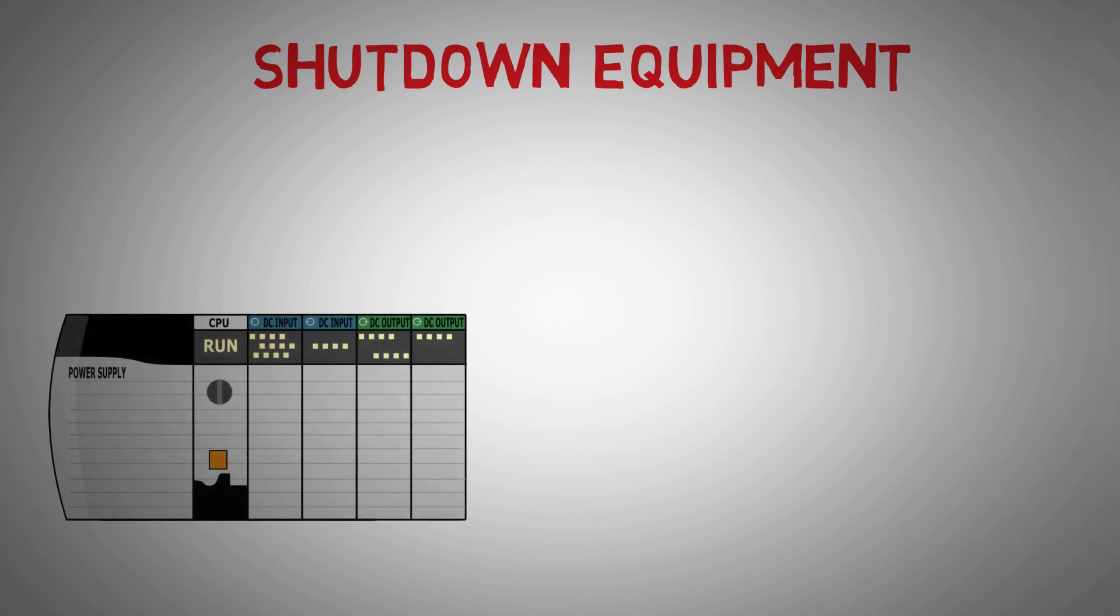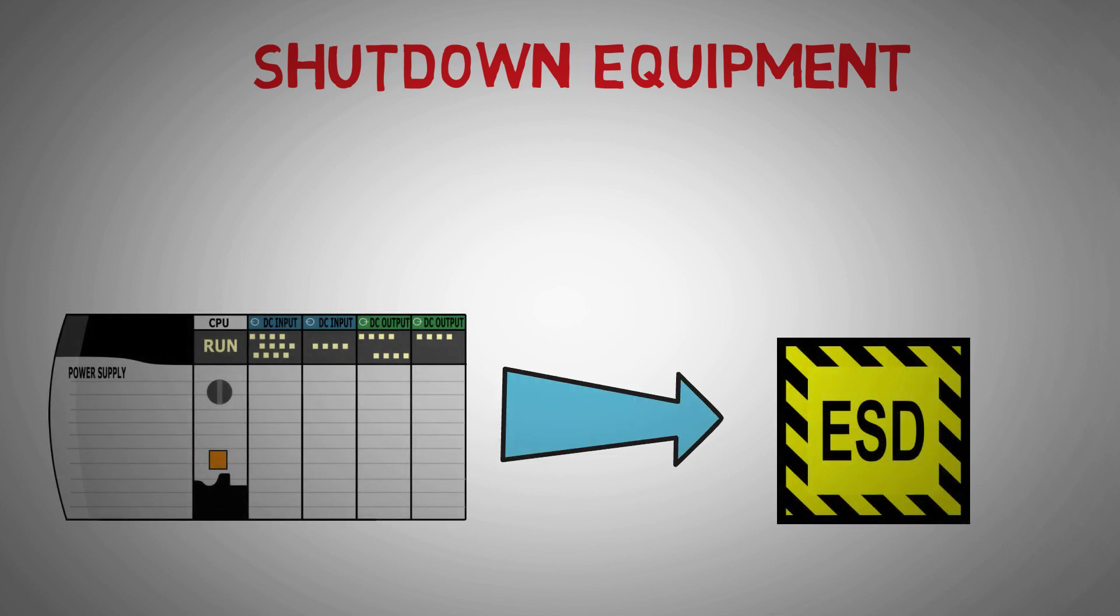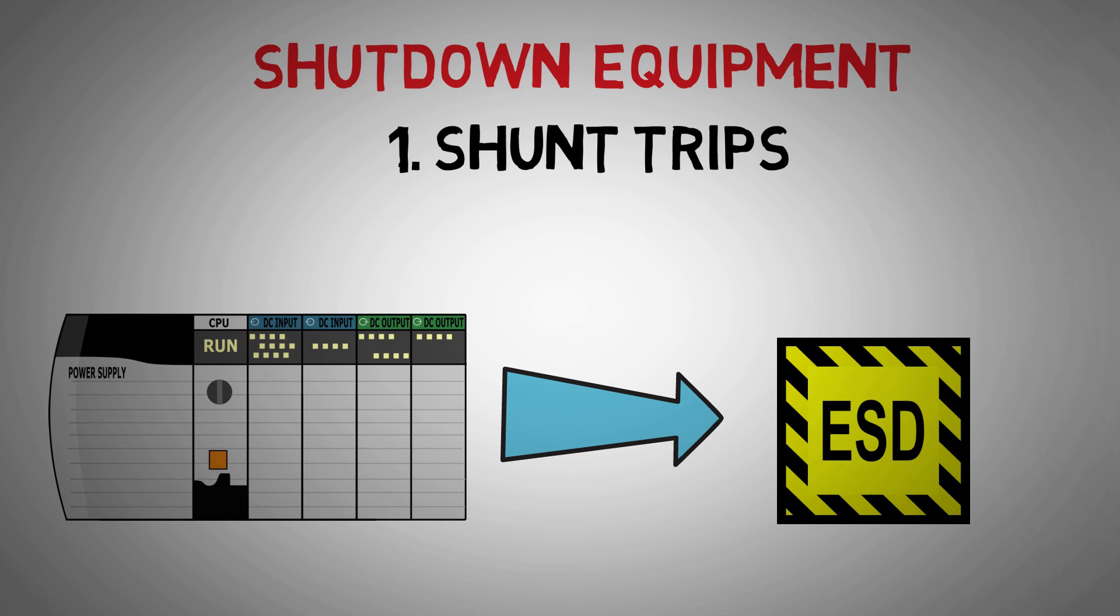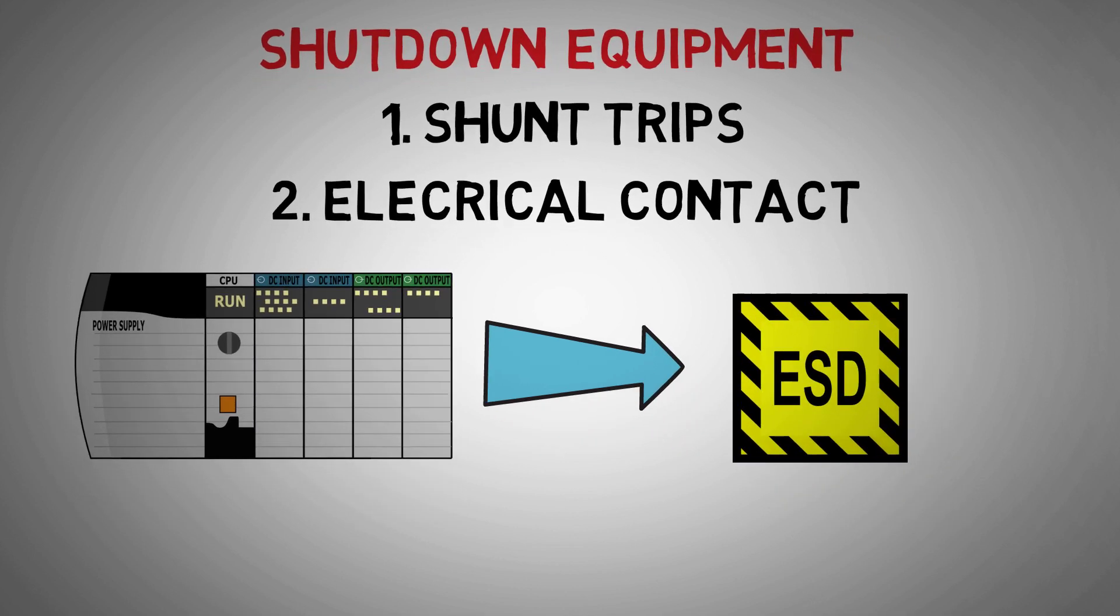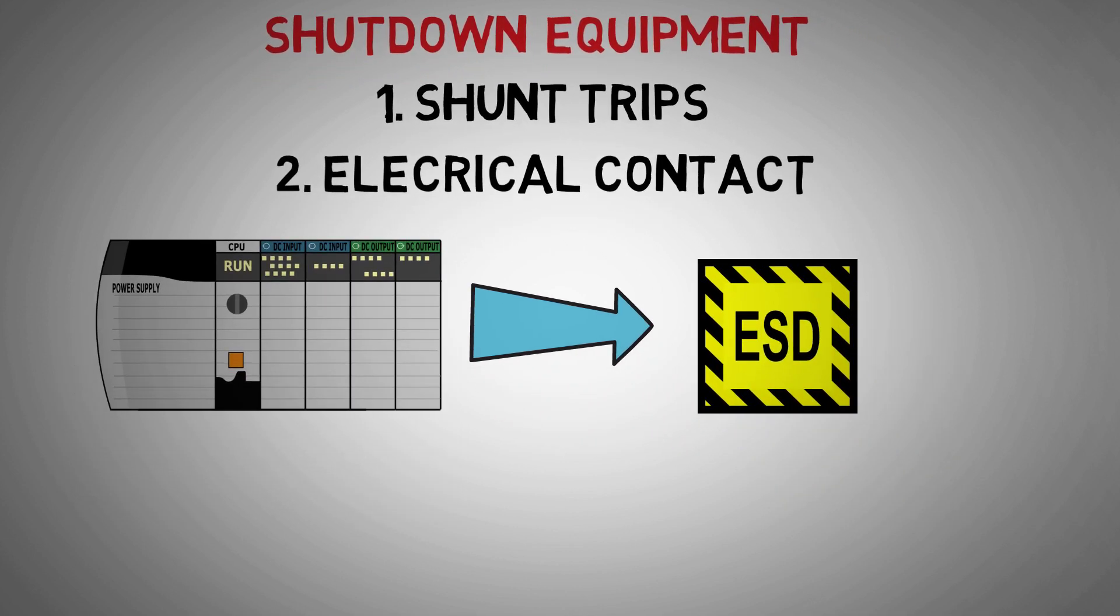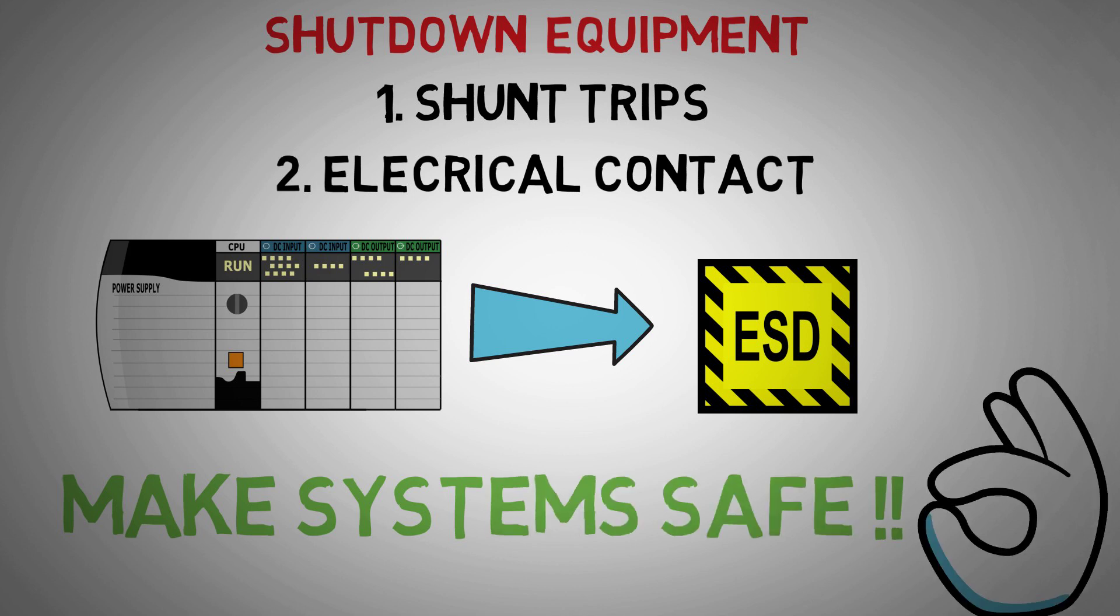Digital outputs can shut down equipment in safety systems through shunt trips or contacts held healthy by the digital output. With these two options, nearly any electrical system can be shut down or change state with a digital output.